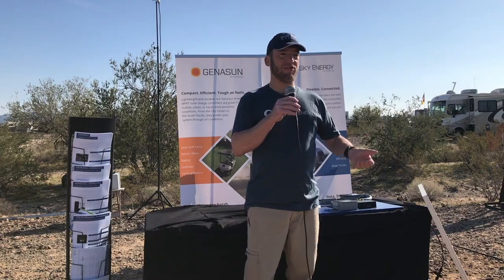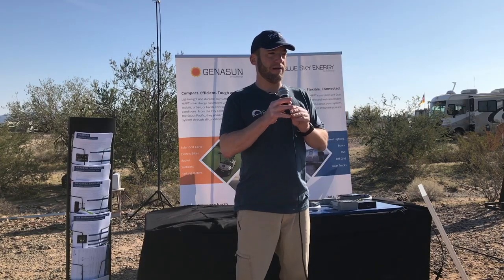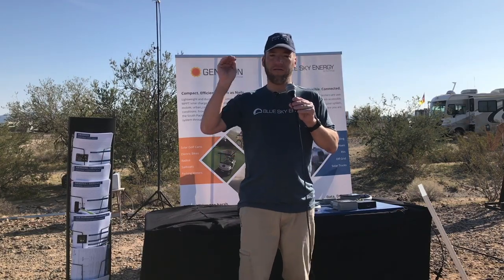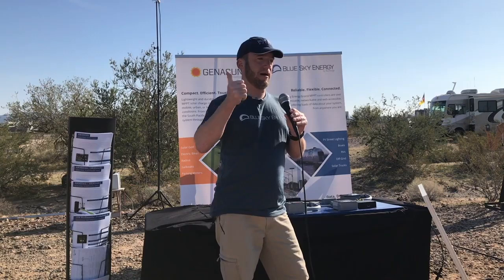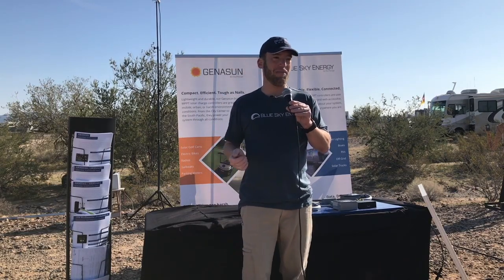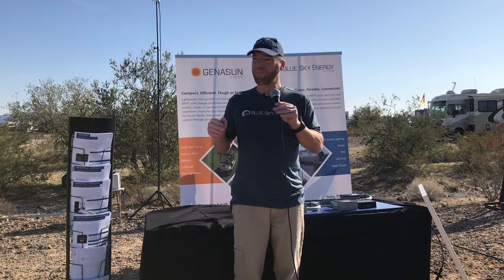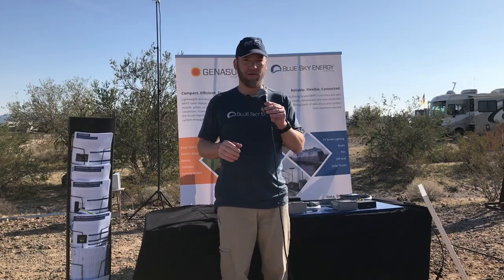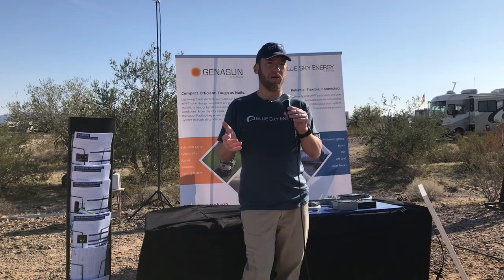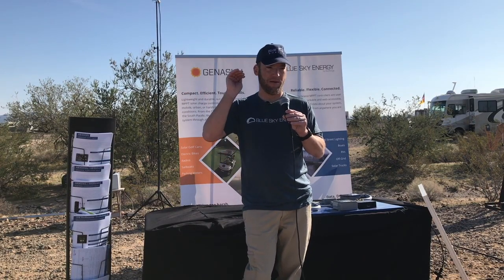Talking about the stages of charging: the first stage, when your controller wakes up, it goes up to your absorption voltage. Now that first set point used to be called constant voltage, then acceptance, now absorption. It's kind of like an AA meeting - if your controller says it's in acceptance mode and another says absorption mode, it's the same animal, the same set point.